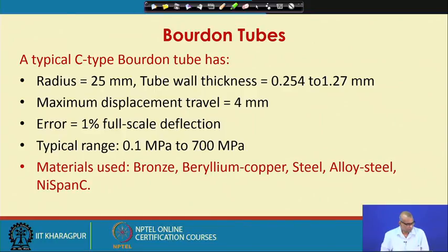Let us look at some data for a typical C-type Bourdon tube. For a typical C-type Bourdon tube, the radius is about 25 millimeter. The tube wall thickness is 0.254 to 1.27 millimeter. Maximum displacement travel is 4 millimeter. Error is within 1% full scale deviation, and the typical range of the Bourdon tube is 0.1 megapascal to 700 megapascal.